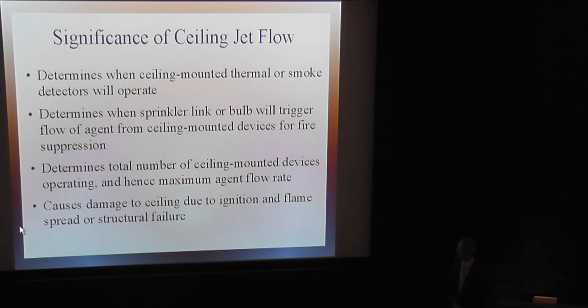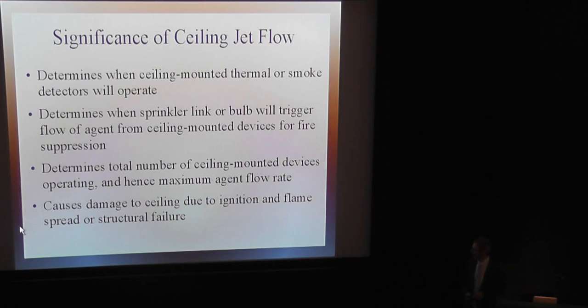That determines how much maximum agent flow is required. If you don't have a system that can provide that flow, then the flow from each device is going to be far below what it was designed for, and the whole system will collapse and won't be able to control the fire. The ceiling jet can also cause damage to the ceiling surface due to ignition if it's a combustible surface, or structural failure even if it isn't combustible.